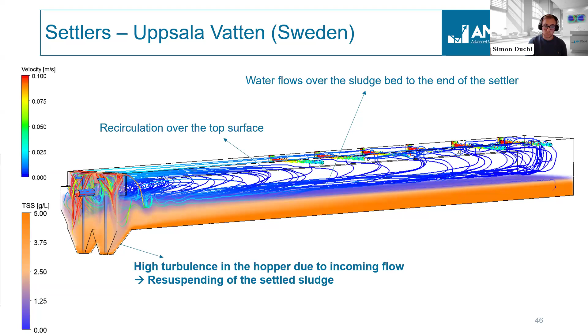The other color is the sludge that you can see, and you can see in the hopper, you don't have a very high sludge concentration. So it's only like 3-4 grams per liter. So you cannot really achieve good settling there due to this high turbulence from the incoming flow. So what we're now trying to achieve is to improve this situation. And we're trying to do some scenarios with, for example, horizontal baffle, but no results yet there because that's still ongoing. And then I give the word back to Roberta.